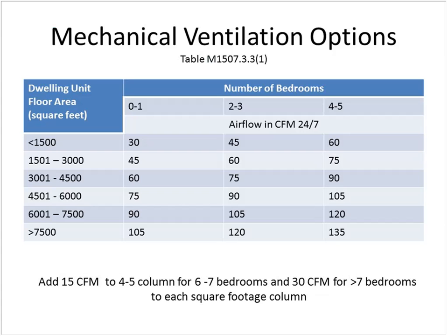It used to be that mechanical ventilation was based on the square footage and bedrooms, and you actually had a calculation where you could use 1/100th of a CFM per square foot, and then 7.5 CFM per bedroom plus 7.5 CFM. Now they actually have a chart in the mechanical code that gives you a range of square footages and bedrooms, and then gives you the required amount of ventilation. And you can see that for the average home that we would see, probably 3 bedrooms and 3,000 to 4,500 square feet, requiring 75 CFM. That is a lot of mechanical ventilation.